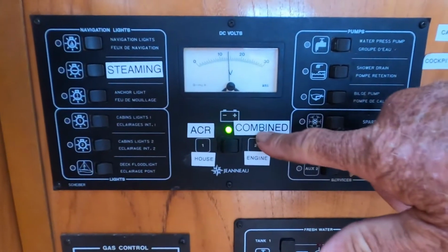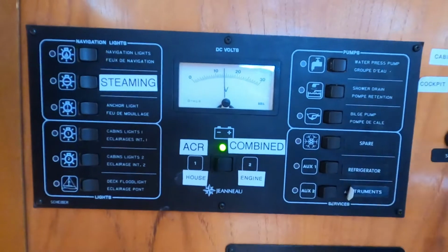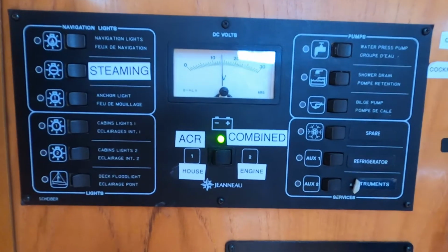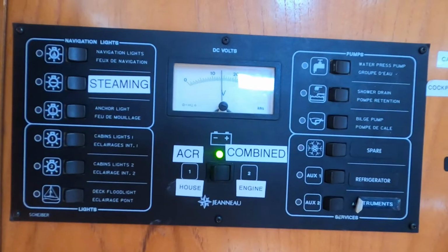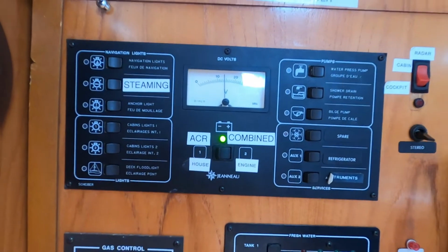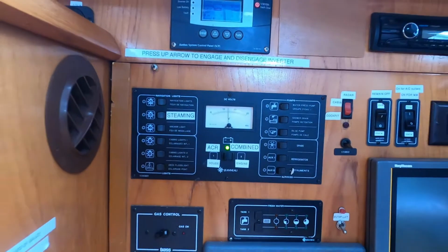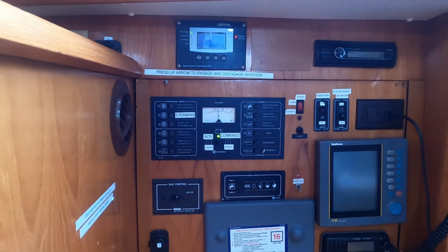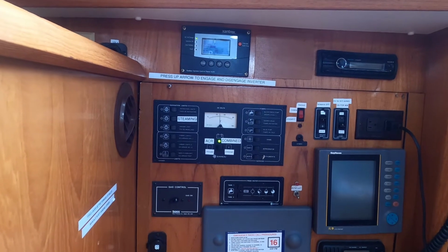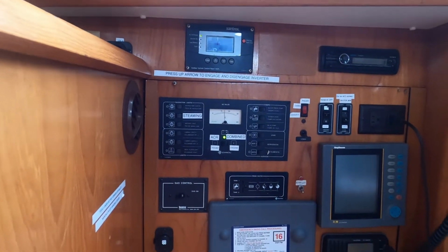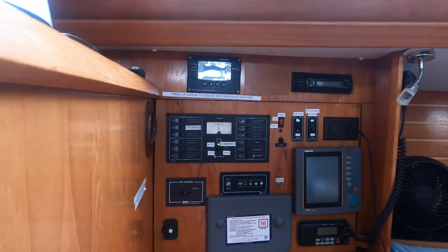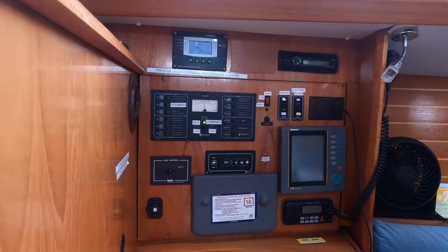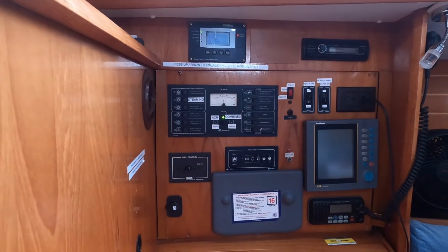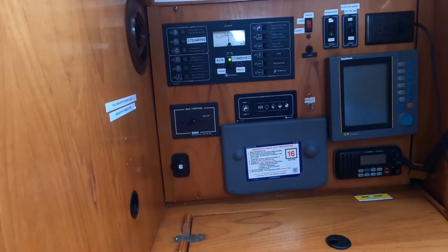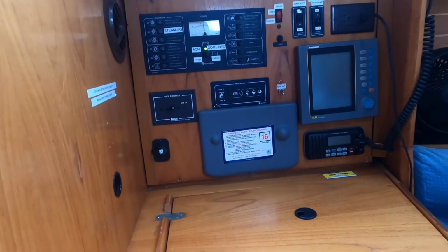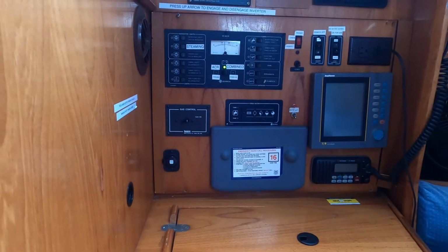When this green light is on, it says ACR combined, meaning everything's working properly. If that light were off, it means one of the batteries has probably gone south, and you'd need to troubleshoot that and find out why you don't have a combined signal, or possibly the ACR itself is faulted. Our experience is those are pretty reliable. Could be bad wiring, maybe a connector's gotten loose, maybe the battery needs water and has dropped below the threshold for the ACR.